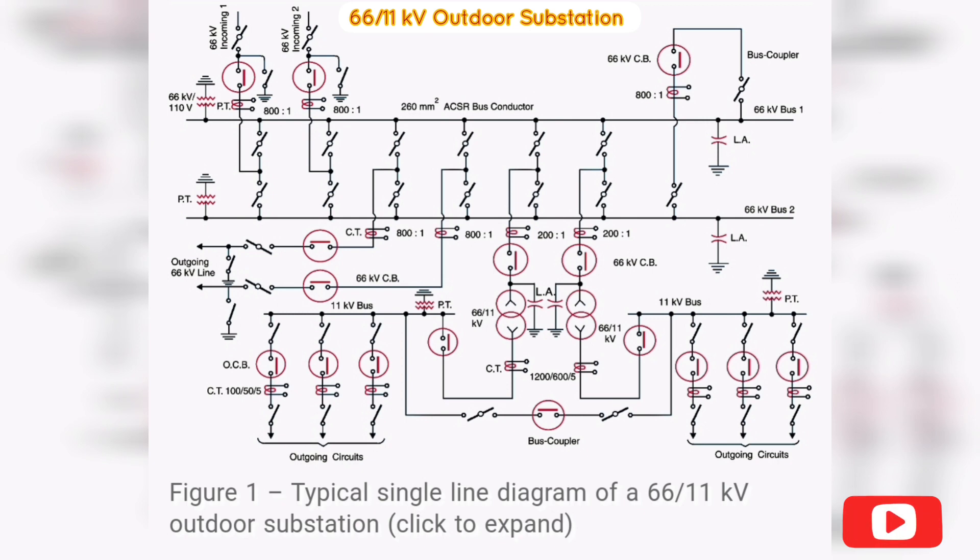Each incoming line is capable of supplying the rated substation load. Both lines can be loaded simultaneously to share the load, or any one line can be called upon to meet the entire load. The double circuit arrangement increases the reliability of the system. In case there is a breakdown of one incoming line, continuity of supply can be maintained by the other line.